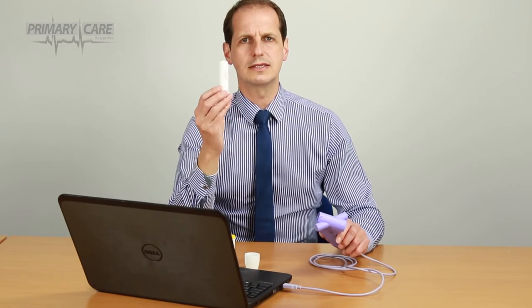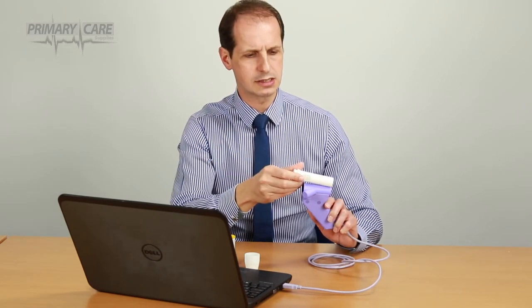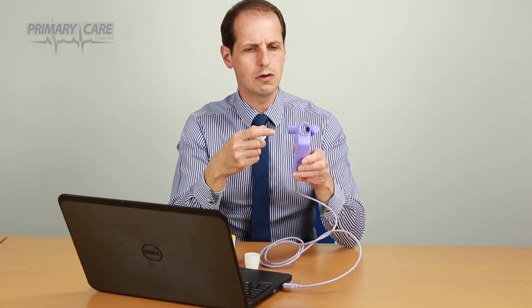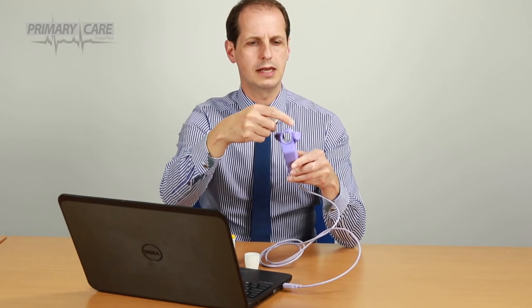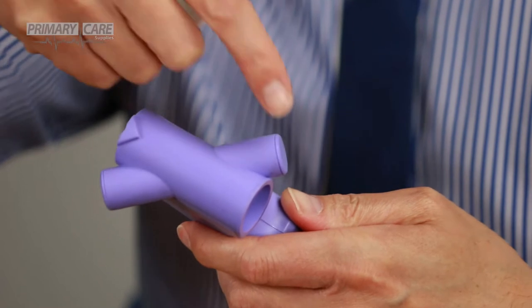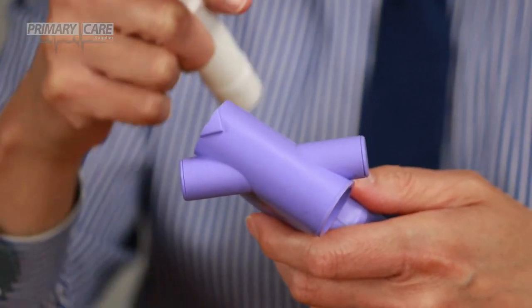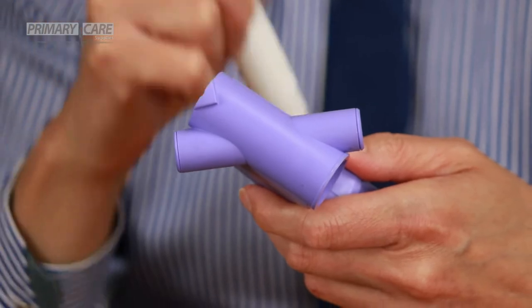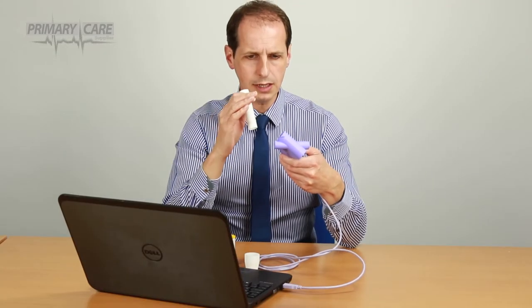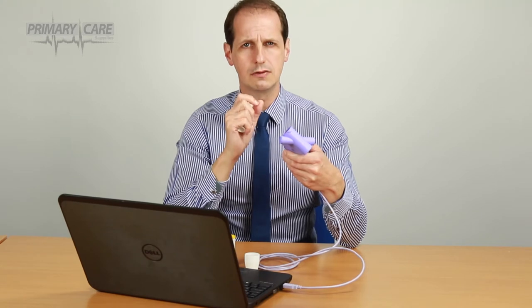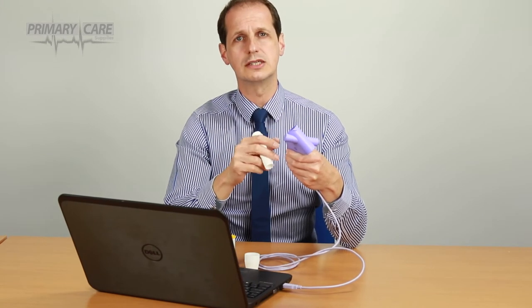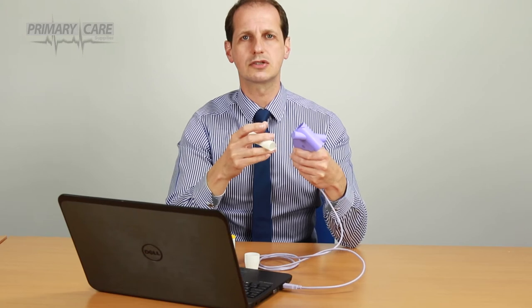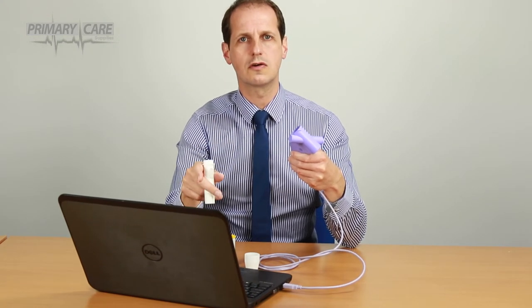So the spirometer itself has three parts to the mouthpiece. So this one is called a Spirette M, and this piece goes into the device itself. Now, the device is ultrasonic, so it has zero moving parts in here, and it bounces sound backwards and forwards across a set distance, about 200 times a second. And because this distance is set, the calibration of this cannot alter. Now, within guidelines in the UK, it recommends that you verify this before each clinic. So you can do that with a 3-litre syringe and the results will be stored into the software.